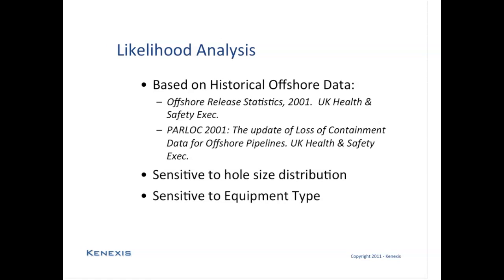Now, all of the information that is collected and presented in the publicly available sources is going to be sensitive to hole size distributions. So for any type of equipment under study, you're going to want to consider the likelihood of very small leaks, medium leaks, and large leaks, essentially with pipe diameter being the largest hole size leak that would be considered. In addition to the hole size distribution, it should be very specific to the equipment type. Seal failures on pumps occur much more frequently than vessel failures. So the leak rates must be specific to the type of equipment under study.